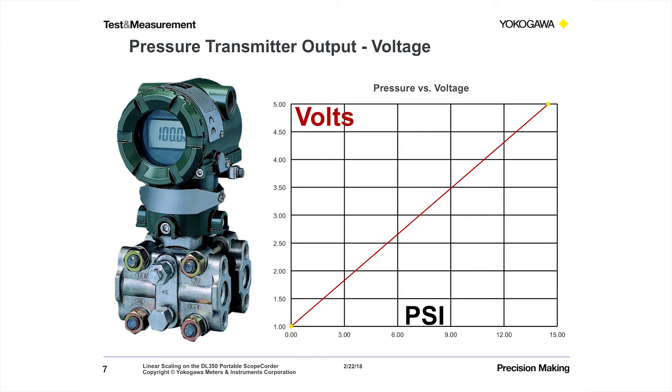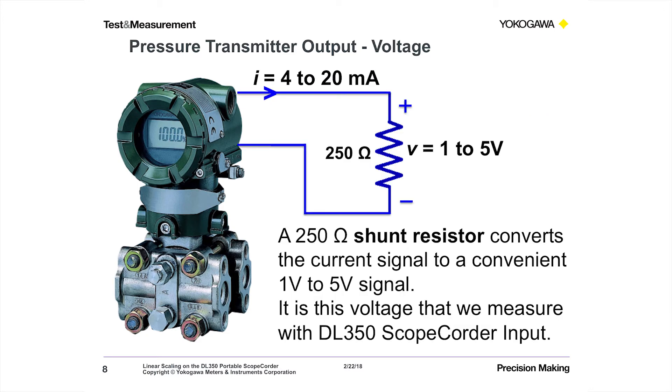With a 250 ohm resistor on the output of the EJA series pressure transmitter, we get 1 to 5 volts. So it's a straight line — it's linear. We want to go from volts to psi. Here's a schematic showing that we're taking the 4 to 20 milliamp signal through the 250 ohms and getting back to a 1 to 5 volt signal.